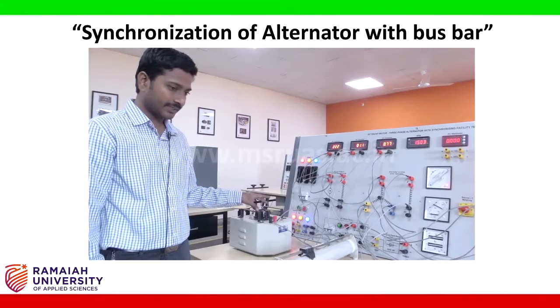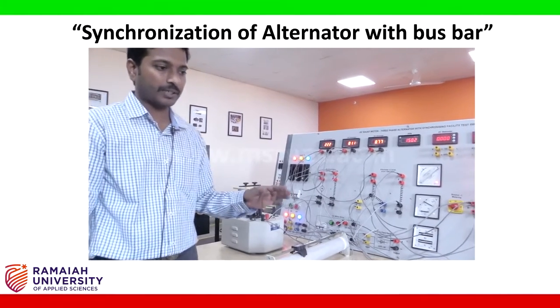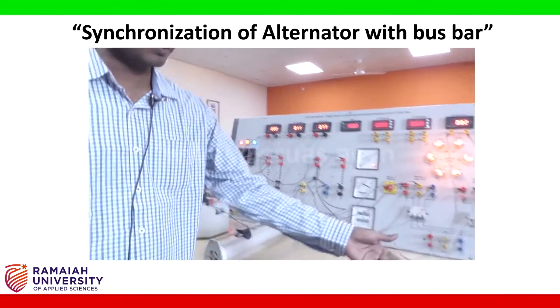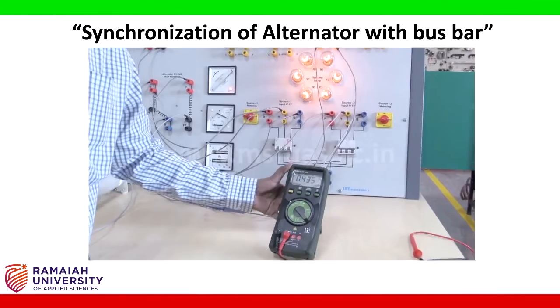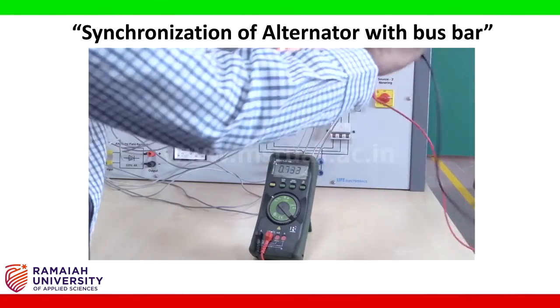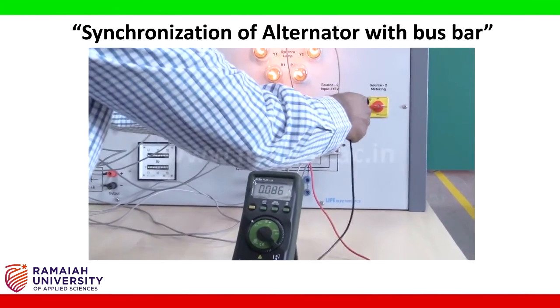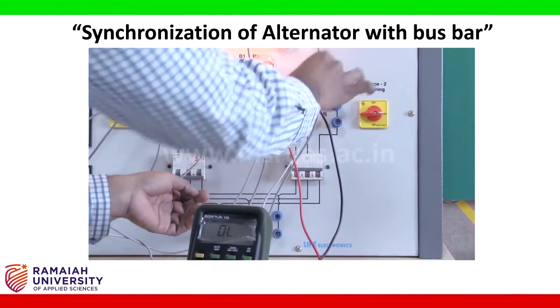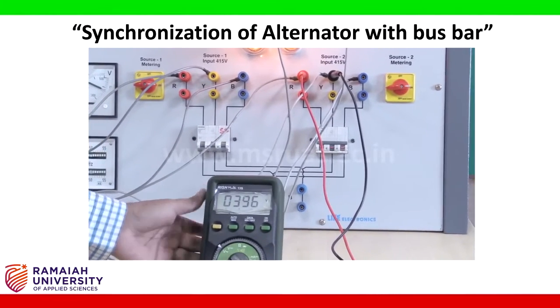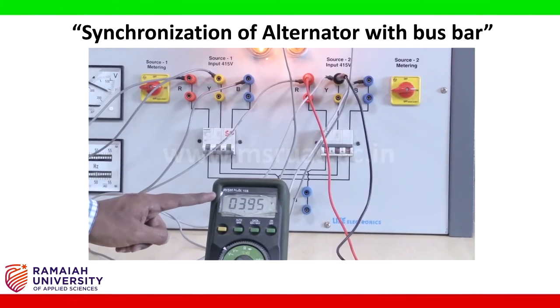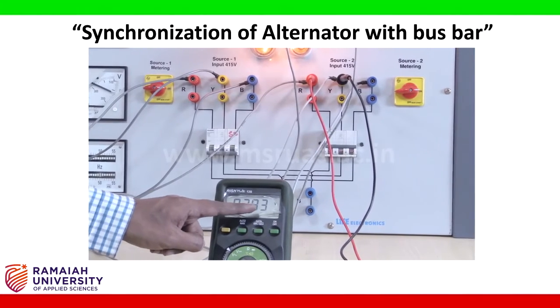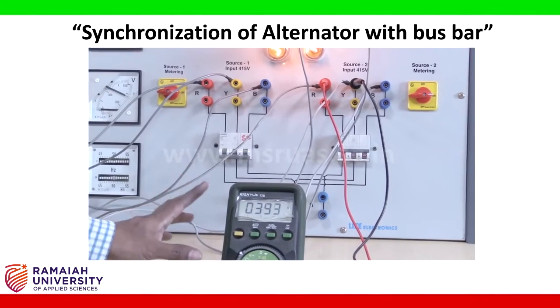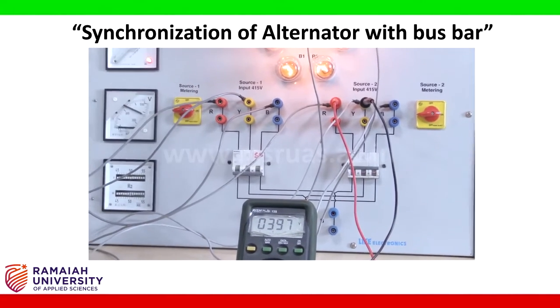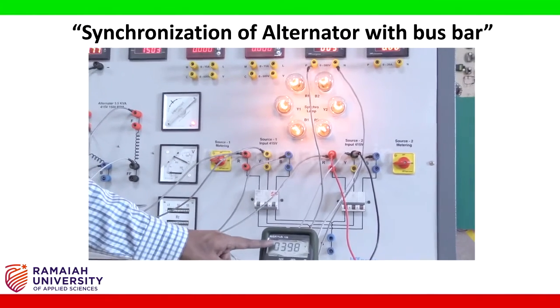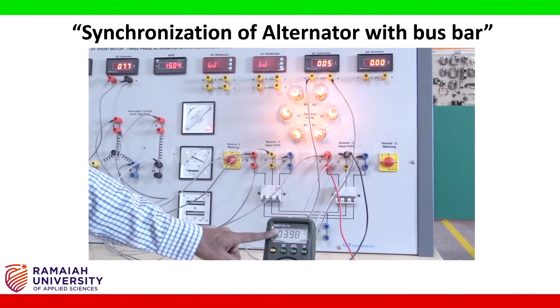Before giving the field excitation, for a more accurate observation of the system voltage, we will take one multimeter and connect it across the supply terminals, that means the bus bar terminals. Now observe the voltage of the bus bar, that is 394, 396, varying. Now we will develop the same voltage in our alternator as we are observing in the multimeter.